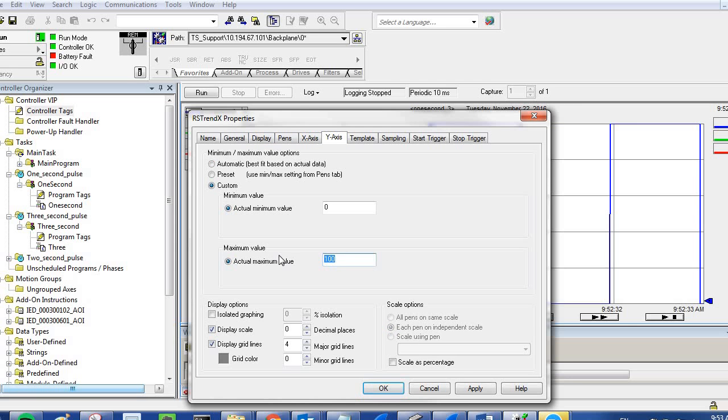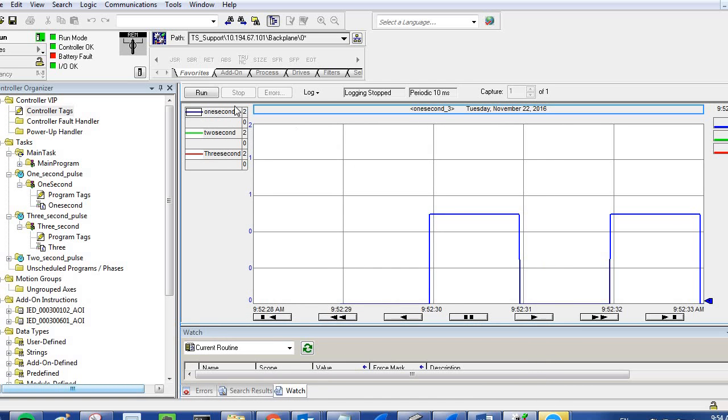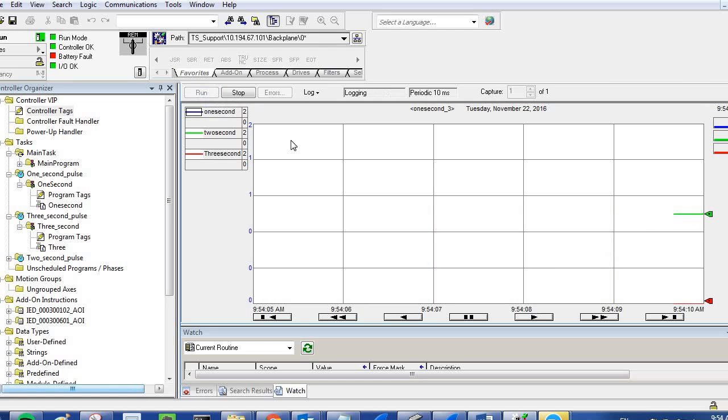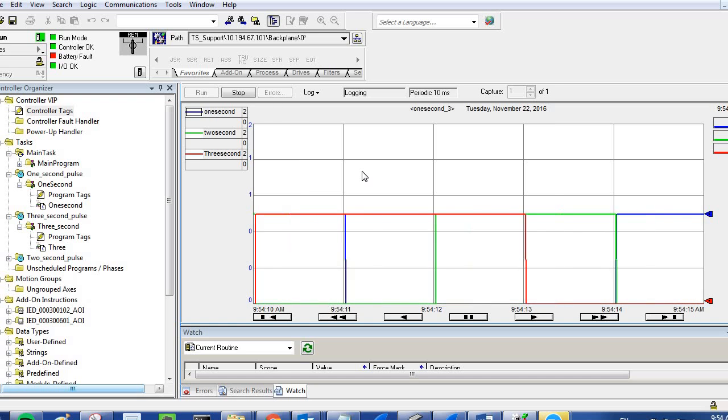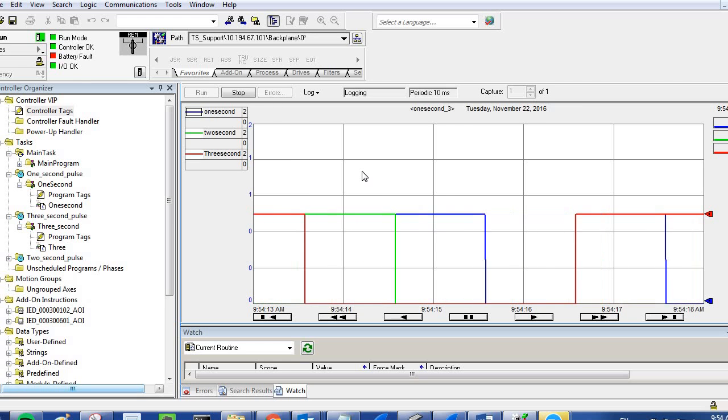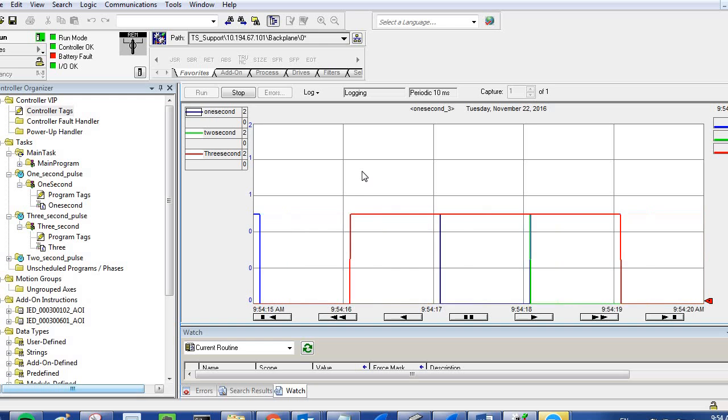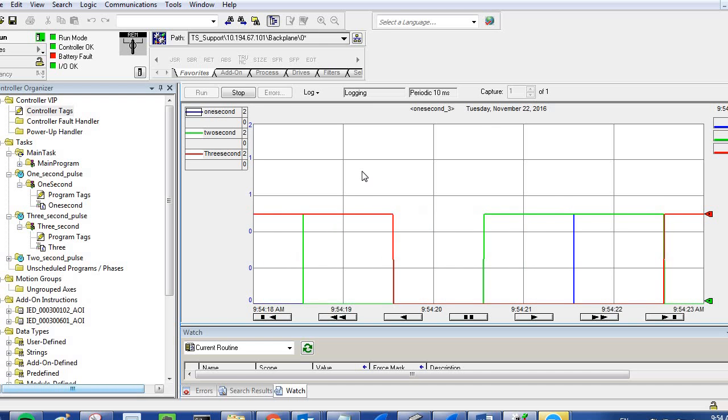The video didn't go into a lot of detail on debug. If you've ever worked with a serial protocol analyzer and actually see all the data coming in, the request coming in, that's typically what the debug window is going to be, in real time. The one drawback from that is, and that's why you're setting it here, is the difference between the debug and Modbus slave. In Modbus slave, you actually have the ability from the gateway to poll the devices in the field and bring back Modbus data.